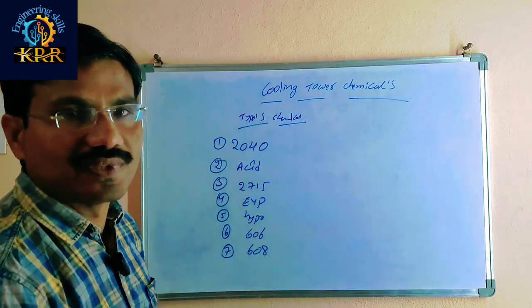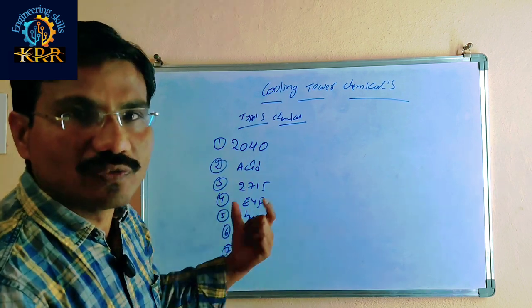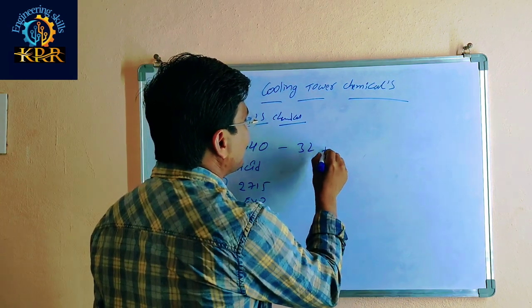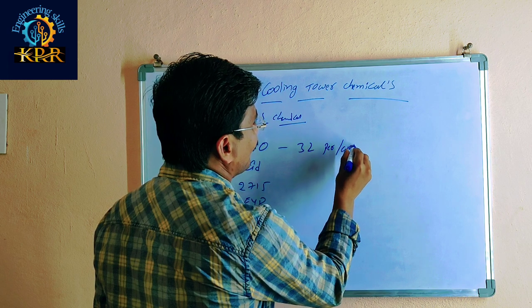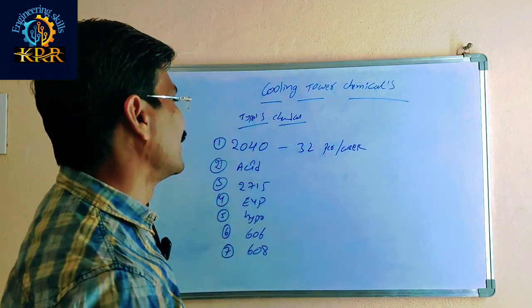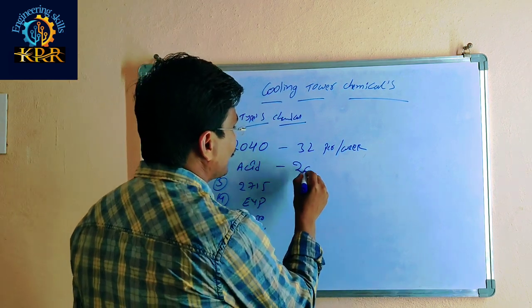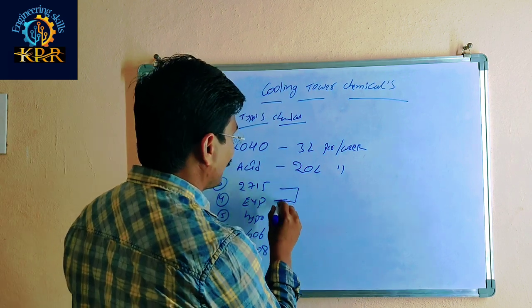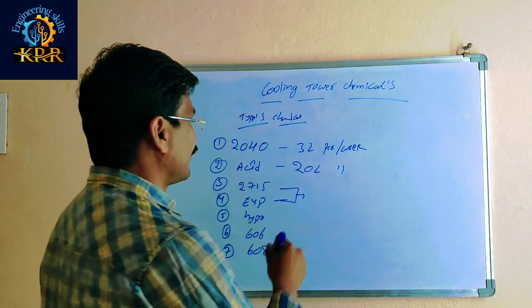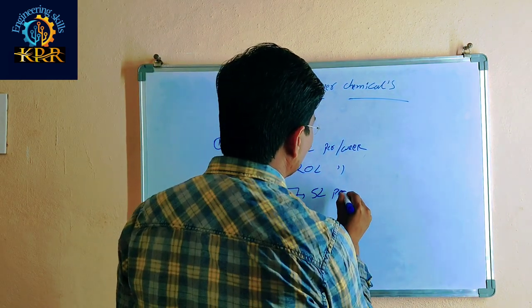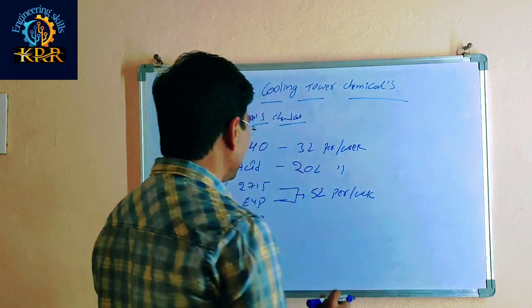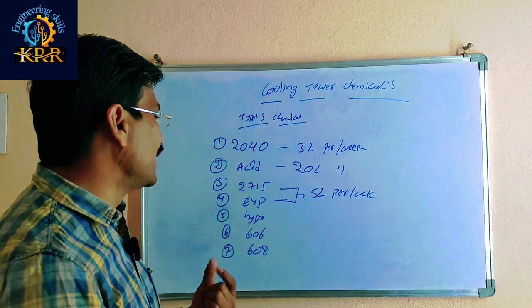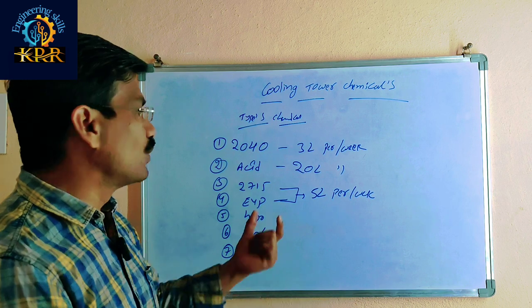These are all the chemicals. The 2040 chemical is used at 32 liters per week. Acid is used at 20 liters per week. 2715 and EVP are used at five liters per week each. These two chemicals are used alternately — 2715 one week and EVP the next week.